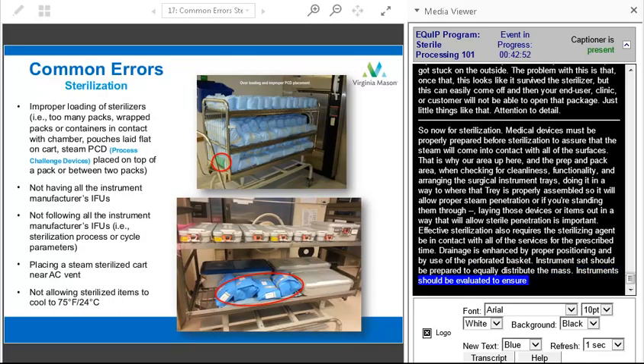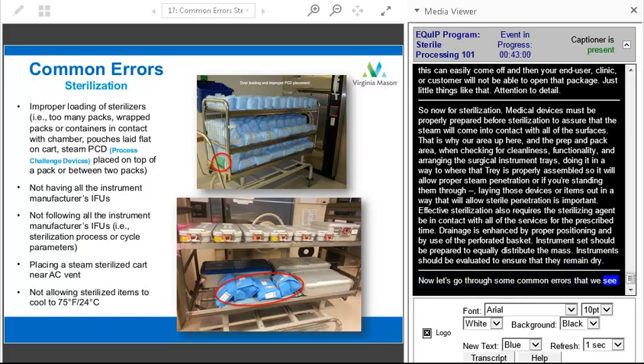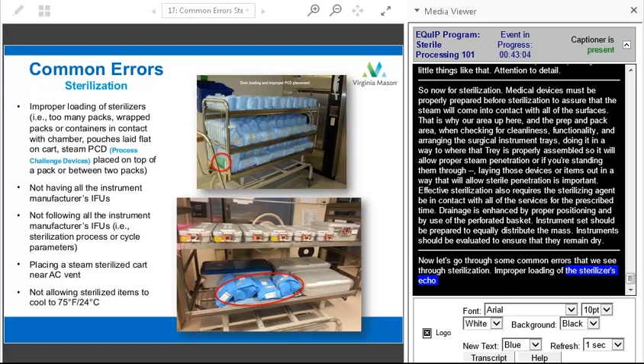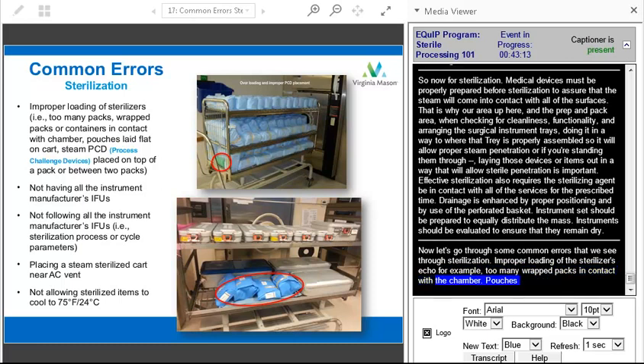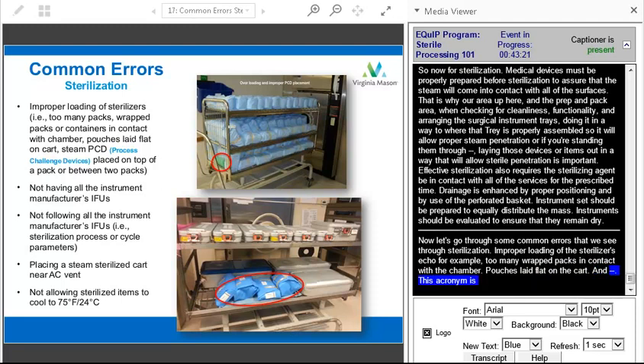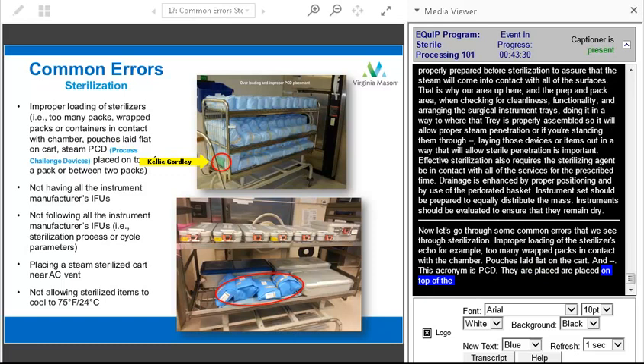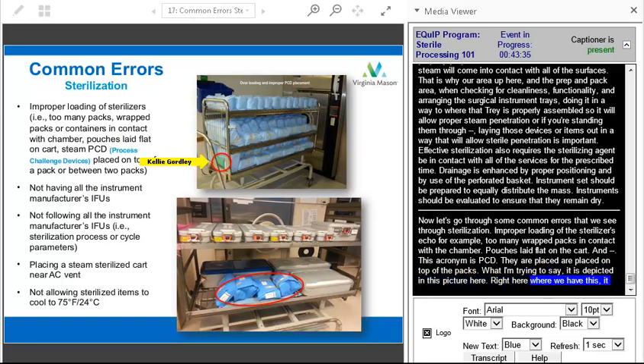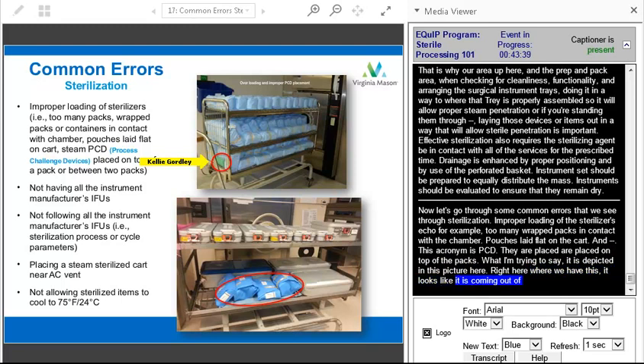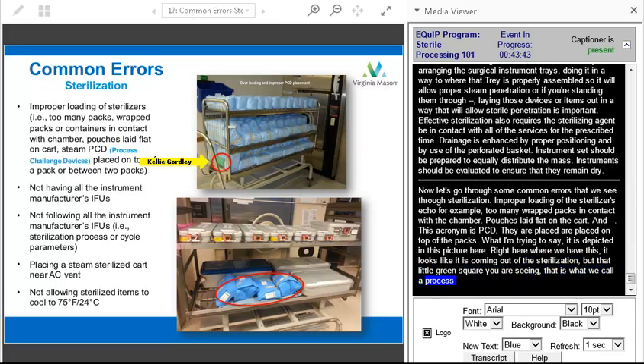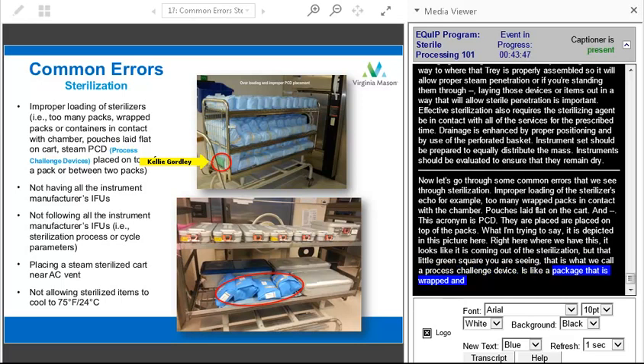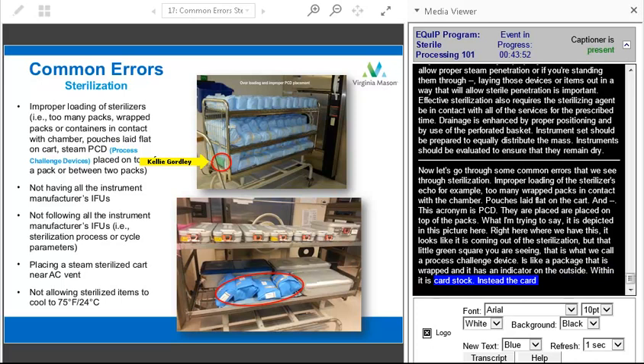All right, so now we go through some common errors that we see with sterilization. Improper loading of sterilizers, for example: too many packs, wrap packs or containers in contact with the chamber, pouches laid flat on the cart, and the PCD, the process challenge device, placed on top of the pack or between two packs. What I'm trying to say in that paragraph is depicted in this picture right here. It looks like it's come out of the sterilizer, but that little green square you're seeing is what you call a process challenge device. It's a wrapped package with an indicator on the outside, and within it is cardstock, and inside the cardstock is a biological indicator and also a chemical indicator.